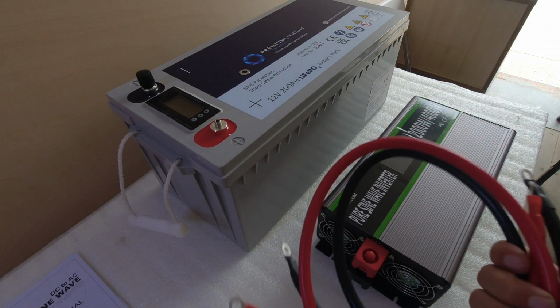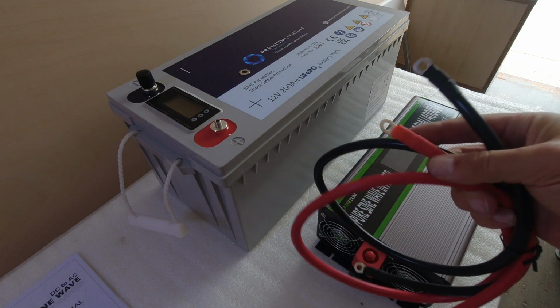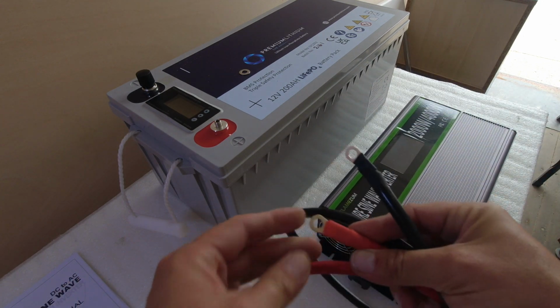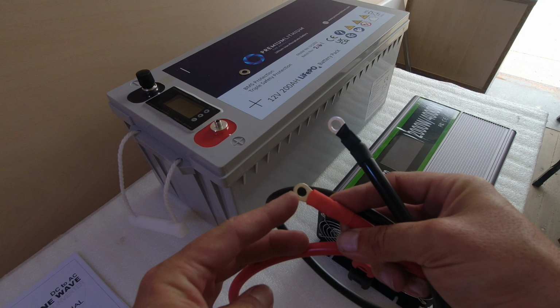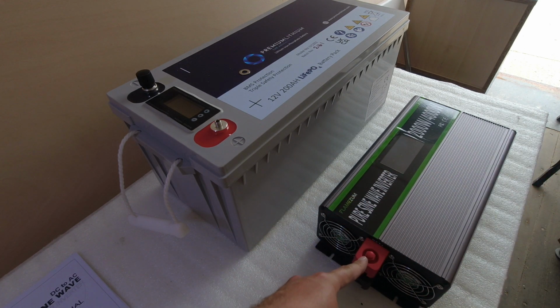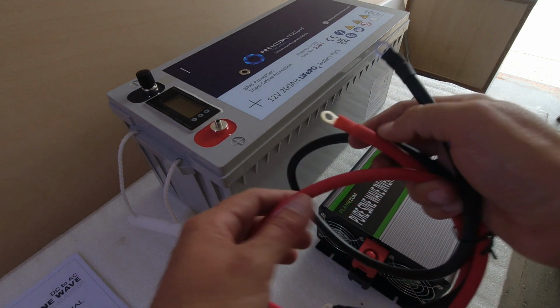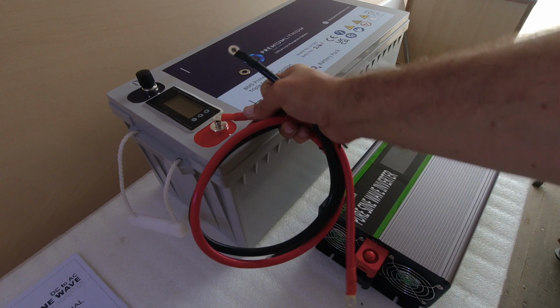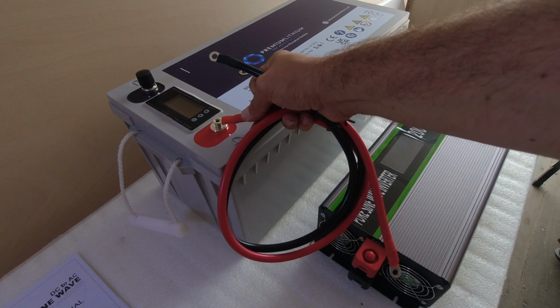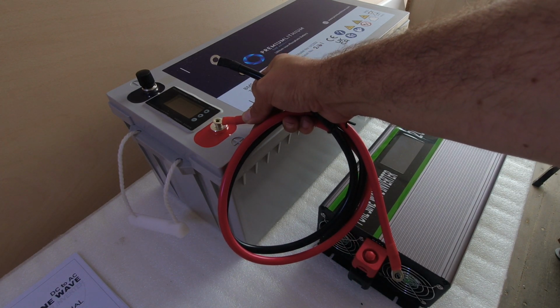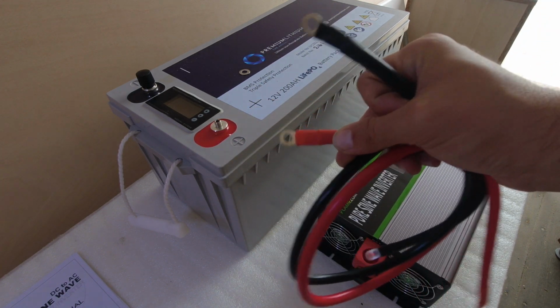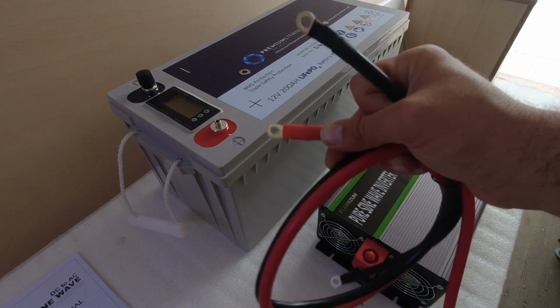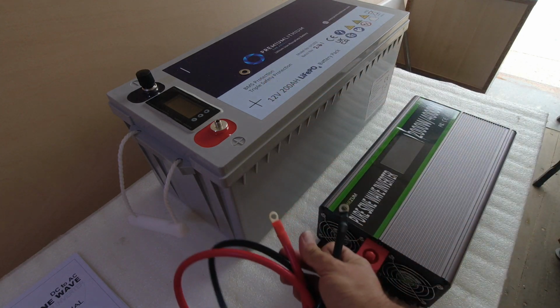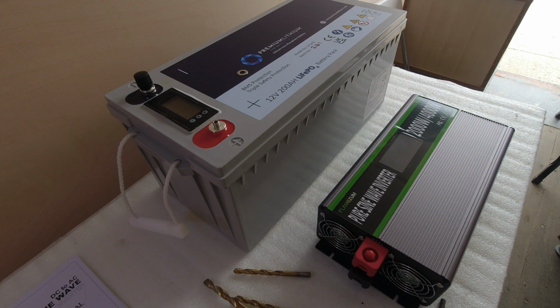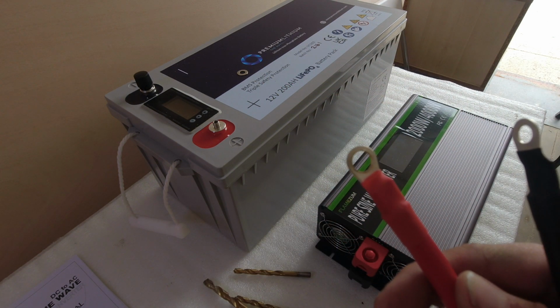The first issue we encounter with this cable is that this connector is for a 6mm bolt, which is on the inverter side, but the battery has an 8mm bolt, so this connector will not fit. I will try to enlarge the hole of the connector just for this test.